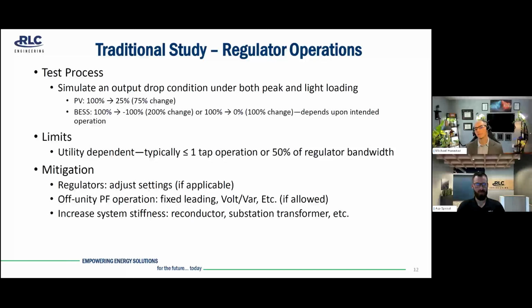So if you have load drop compensation schemes on your circuit, it can be better to actually look at the number of tap operations that are occurring rather than using a 50% of regulator bandwidth criteria. It's just a note. Mitigation, you can adjust the settings sometimes. You can use off-unity power factor, so fixed leading, volt-var. You could add potentially a StatCom to help regulate the voltages a little bit, or you can increase system stiffness with reconductor, substation transformers, etc.